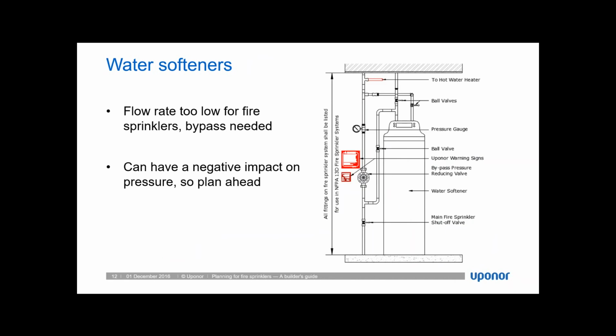Now I'm going to talk a little bit about water softeners and how they can be incorporated into a sprinkler system without having a very large impact on the performance of your sprinkler system. Typical water softeners will not have a flow rate high enough for sprinkler system demands. And this is also true of filtration devices. They do exist, but as is probably expected, they're going to be more costly than a standard water softener.